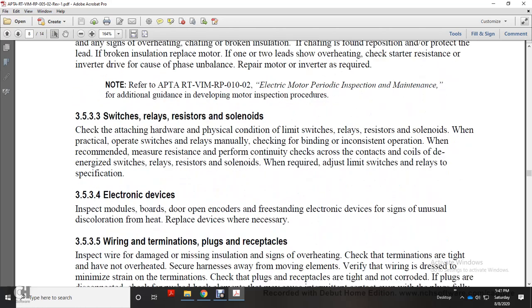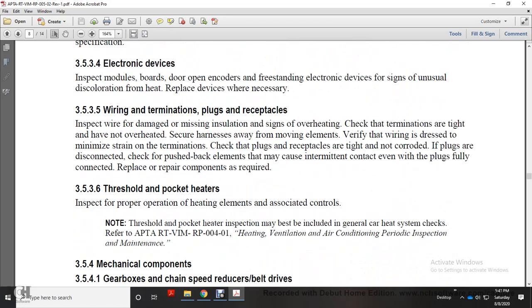3533, switch, relay, resistor, solenoid. Check the attaching hardware and physical condition of the limiting switch, relay, and resistor solenoids. When practical, operate switches and relays manually, checking for binding and inconsistent operation when recommended, measure resistance. Perform a continuity checks across the contacts. Go over the de-energized switch, relay, and resistor solenoids, adjusting limiting switches and relays to specification. 3534, electronic device, inspection module boards, door open encoders, and freestanding electronic devices, looking for signs of unusual discoloration from heat. Replace the device when necessary.